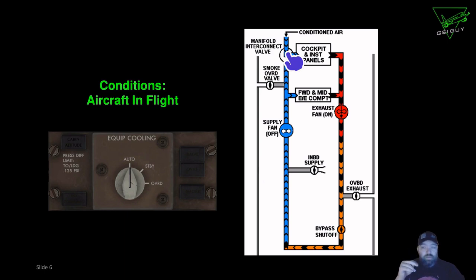And that does pretty good for us because now we have cooler air coming into the system. And that's what we all want. We want it to be cool in there because if it overheats, you start to lose stuff. And we don't want to do that. We want to keep it as cool as possible. So even though I don't have that supply fan running anymore, I have that exhaust fan that's able to pull that conditioned air through this system. Okay.